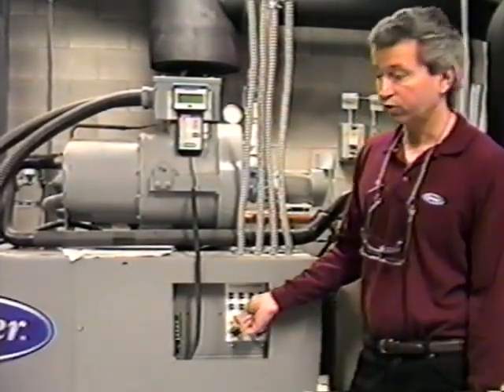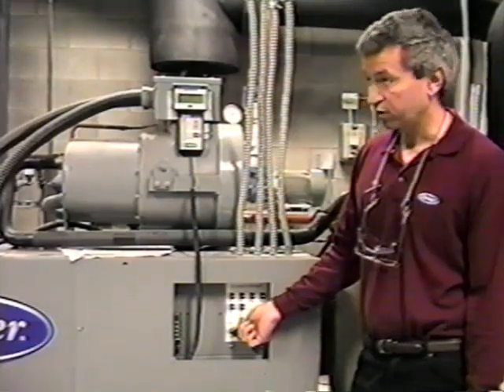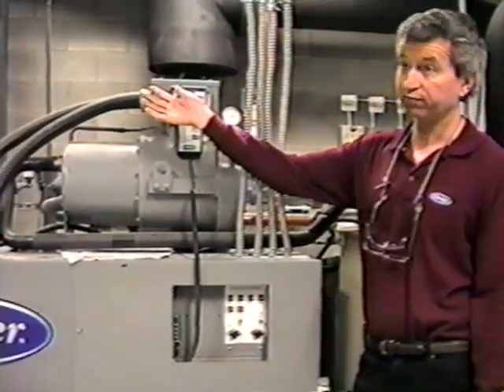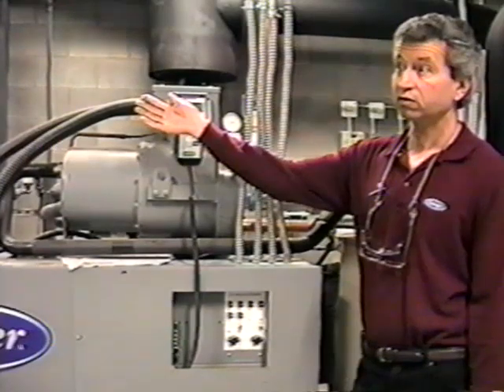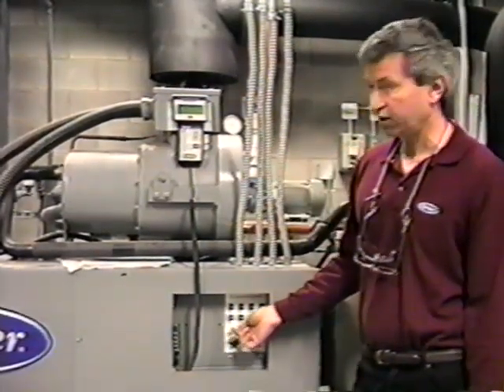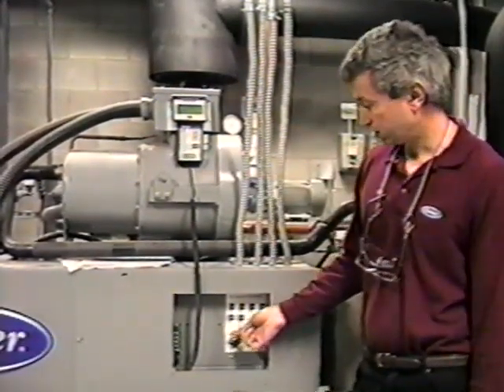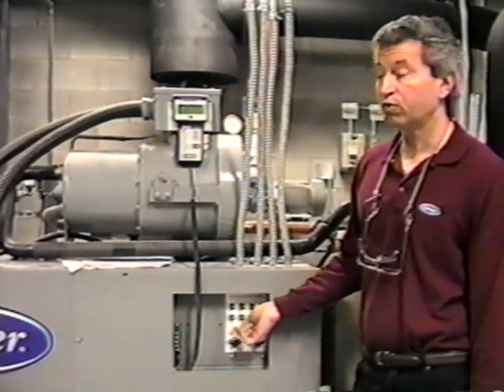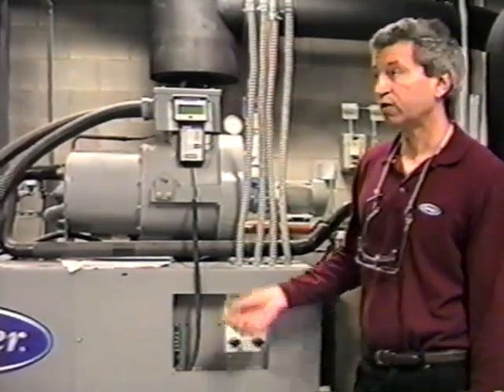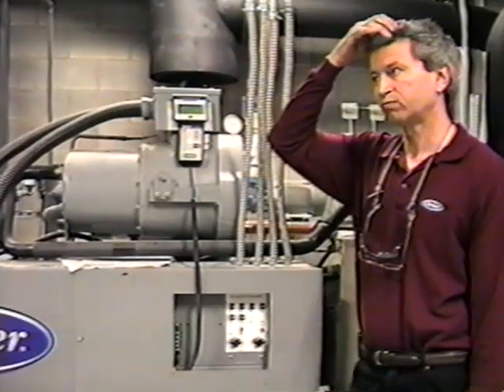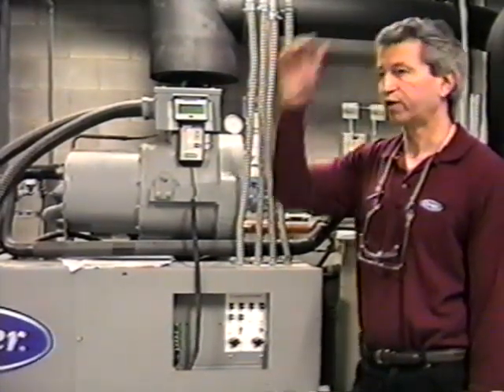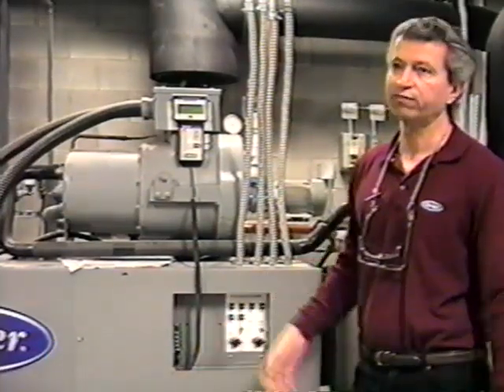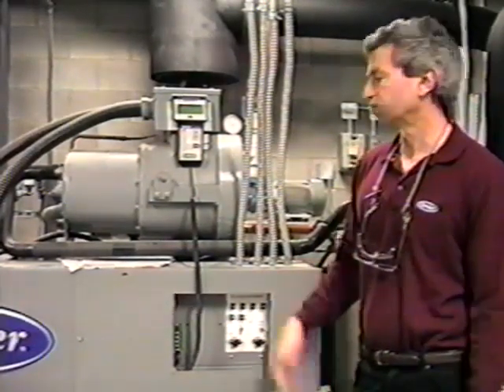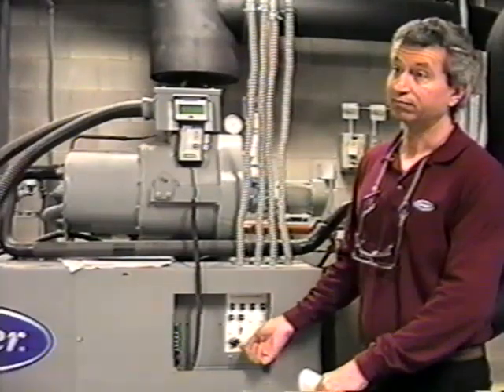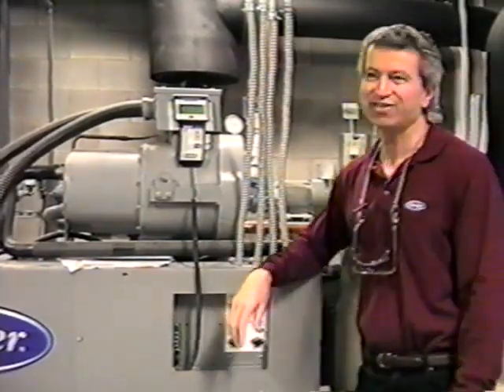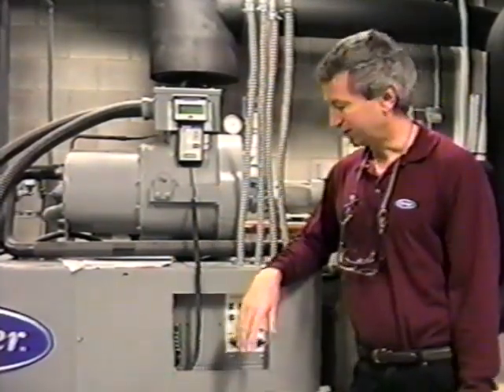So at any time you can turn it off. And then in enable mode, it's going to run regardless of what the smart drive is wanting it to do. So you probably only want to be at any given time in the remote contact mode or the off mode, because the smart drive, I believe, controls the pumps. Right. So you don't want to try running it in enable, even though there are safeties that will probably not let it start. It's best not to test the safeties out in that manner.